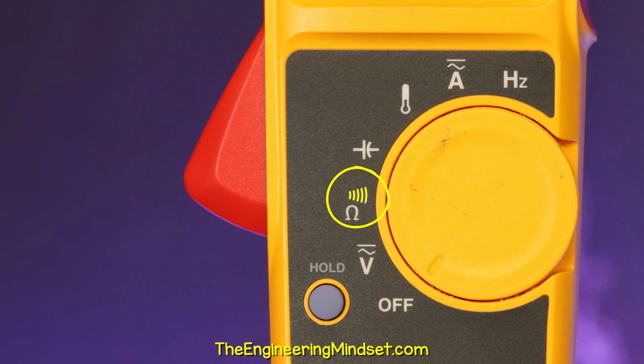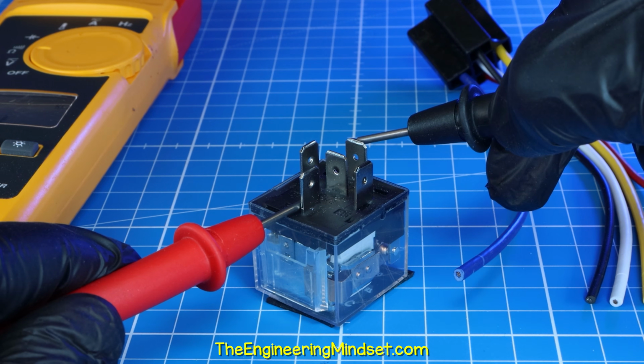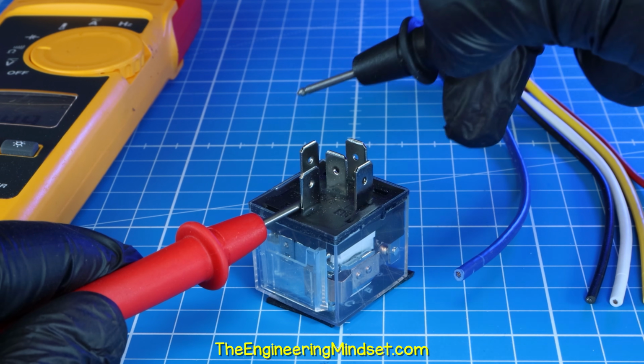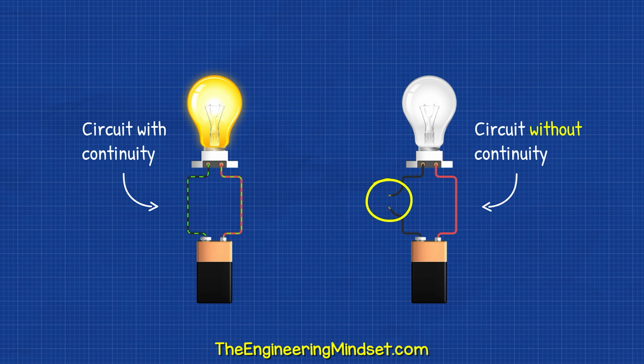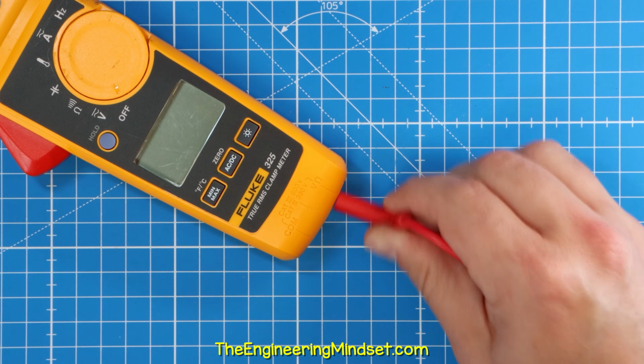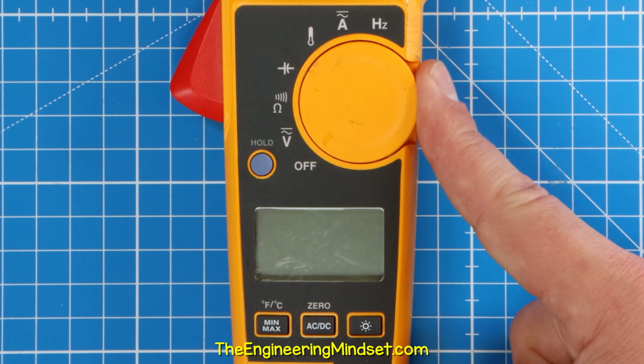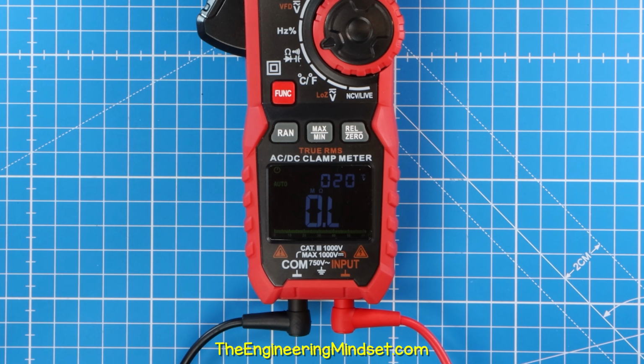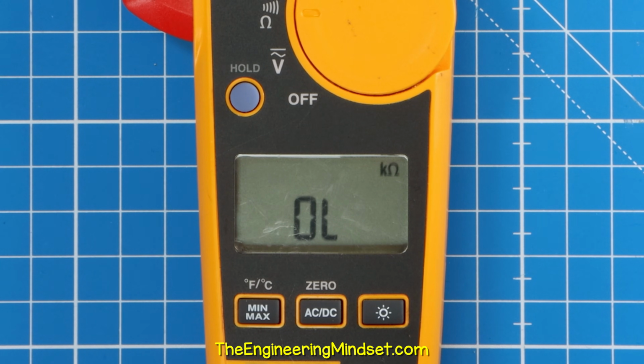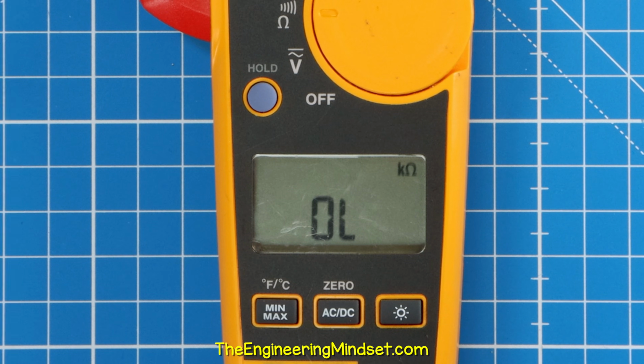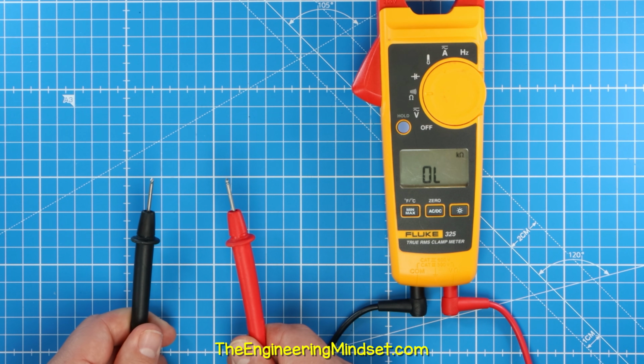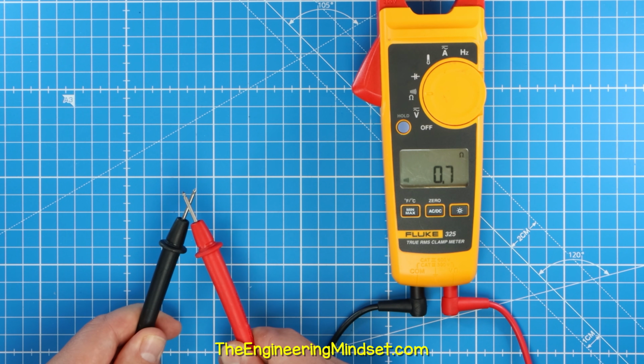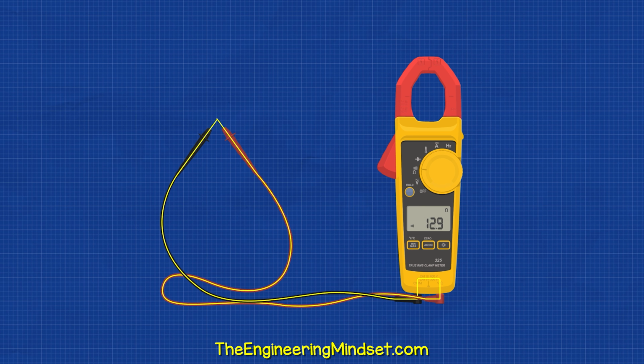We use the continuity function to test if there is a connection between 2 points in a circuit. If so, it means electricity can flow. Just insert your leads into the meter and then select the continuity function. Some meters require you to select the function from the options. The meter defaults to OL for open loop, but if we touch the probes together, we should hear a tone, and that's because we have completed the circuit.